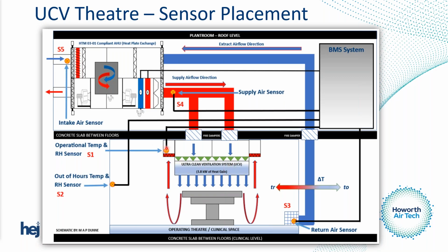So if we have the sensor there as opposed to there, the readings for the dual temperature and humidity stat will be much more accurate back to the theatre control panel, because one of the requirements of validation is that we get plus or minus 1 degree from the calibrated instrument in the centre of the room to the theatre control panel, and plus or minus 5% on the relative humidity from the centre of the UCV to the theatre control panel.